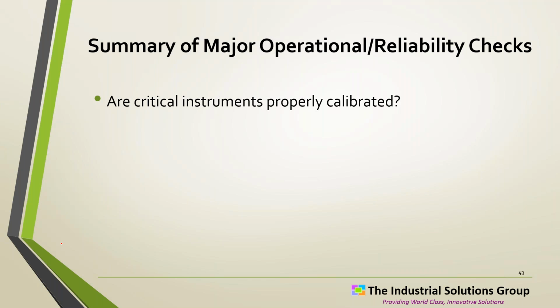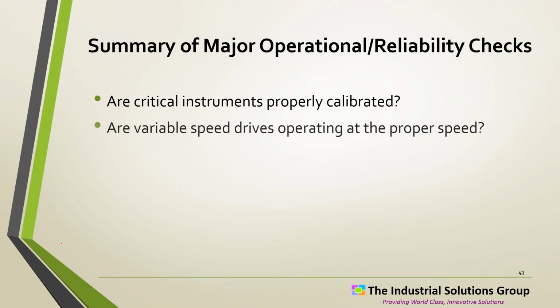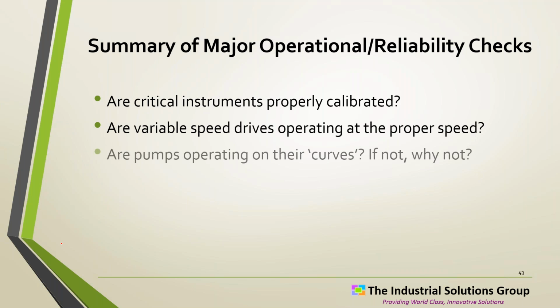So, wanted to summarize some operational reliability checks. We need to make sure that we have instruments calibrated. Variable speed drives, which that one screen that I showed had, are they operating at the proper speed? I don't remember the last time I've seen any cross check, from a control system say. I see a lot that say, yep, it's operating at 85% speed. But then I see a lot of those that also have differential temperatures that are too low, so I know there's a balancing problem so there's nothing that really flags, hey, it shouldn't have to operate at this speed. It is, but it shouldn't have to.